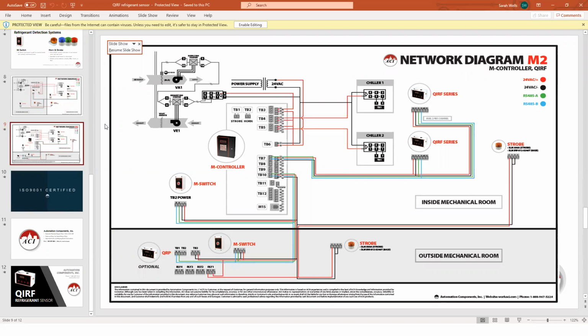Usually what I've found in the specs is, from the gas control system, the fan might be running normally at 10%, and the sequence of operation shows that if gas is detected, it sends a relay signal to go to 30%. Once that relay signal is made, the fans go to 30%. If it goes to the next alarm level, it might go to 80%, or whatever it is. Then once it drops below that, the relay opens, the fan drops back down to 30, and once it goes below that, it goes back to its normal operating level of 10.